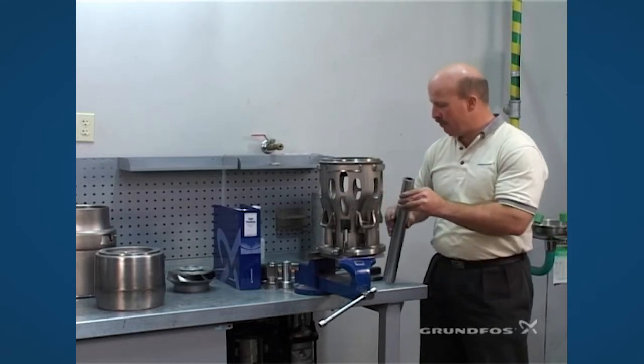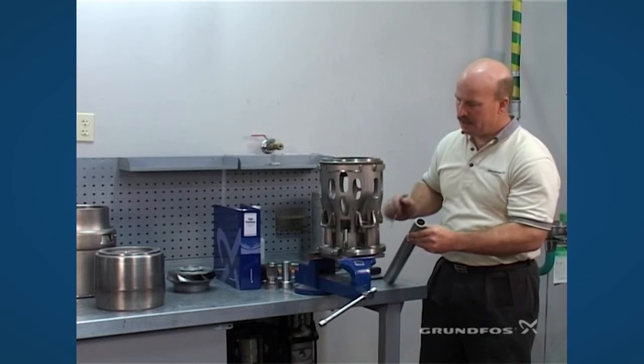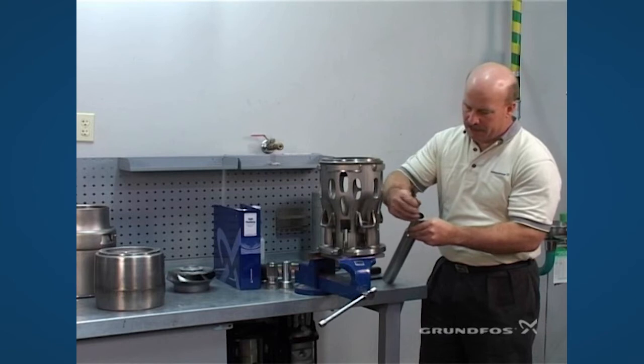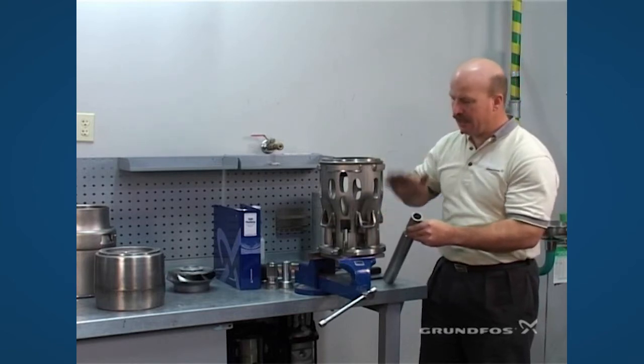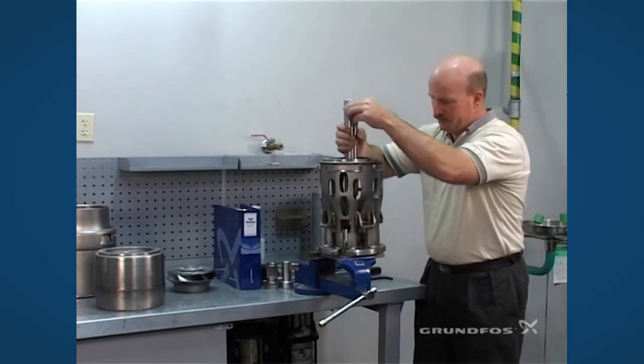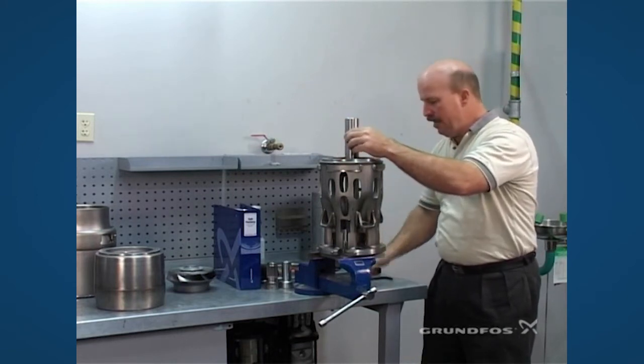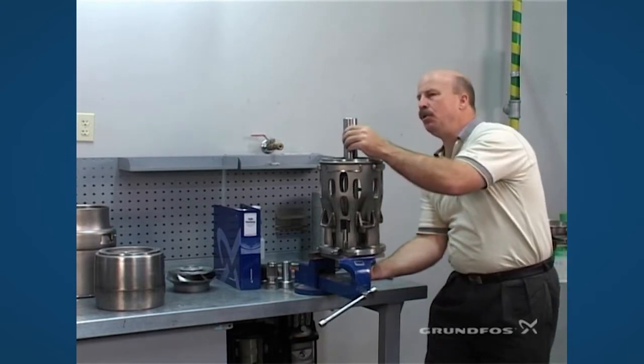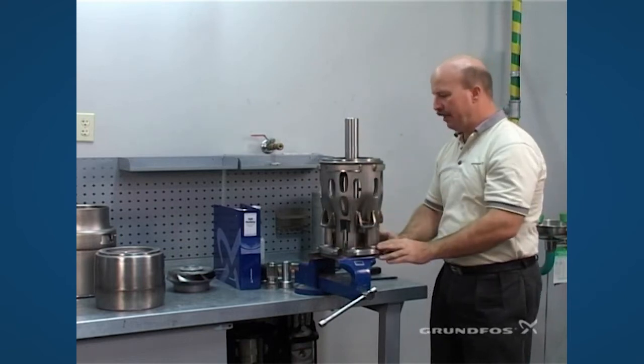Just like we did in the last series from the 625 to the 800S that is built on the spline spacer, we want to remove the O-ring out of the coupling so that it will freely slide down on the spline spacer. Put this in place and using the bolt, secure the bolt up and through the build plate. Ensure that the shaft does not move while it's in place.